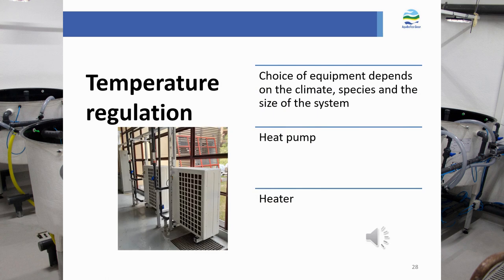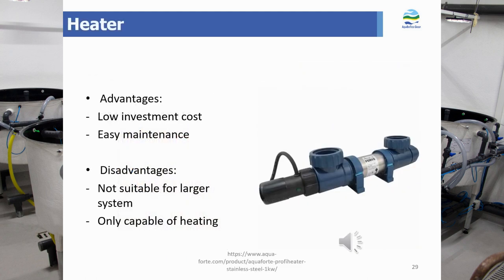Temperature regulation in a RAS may be necessary depending on the climate and the cultured species. Equipment selection also depends on system size. Heat pumps, plate heat exchangers, and heaters are the most commonly used options. Heaters are one of the simplest solutions — comparatively cheap and easy to operate and maintain — and are particularly useful in small systems. However, they are not suitable for large systems, require multiple units, and are only capable of heating, not cooling the water.